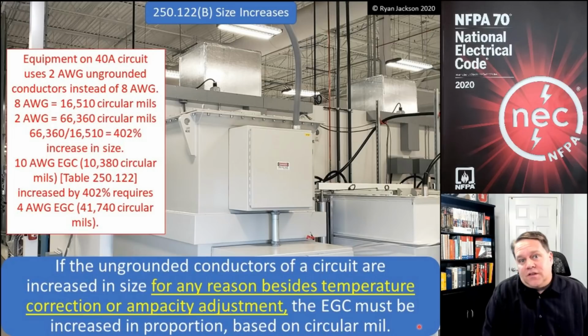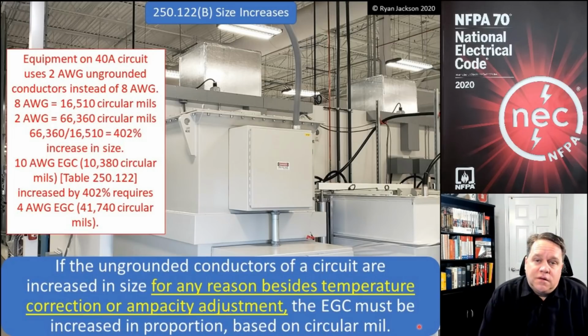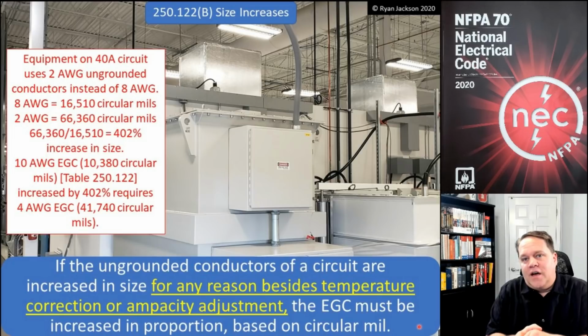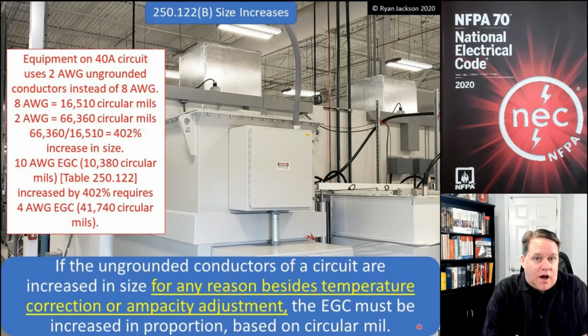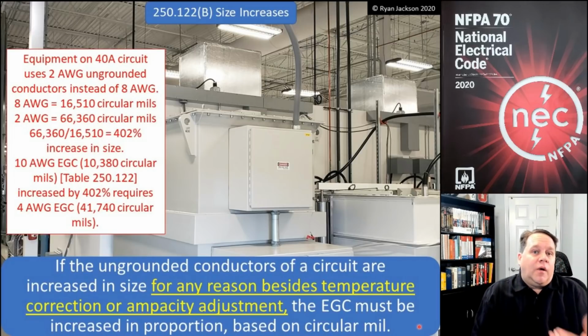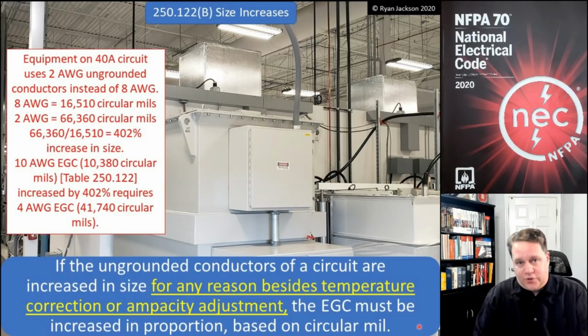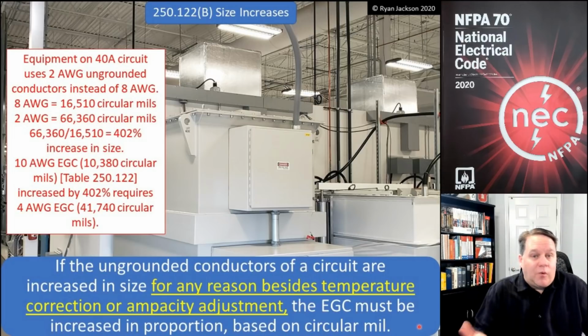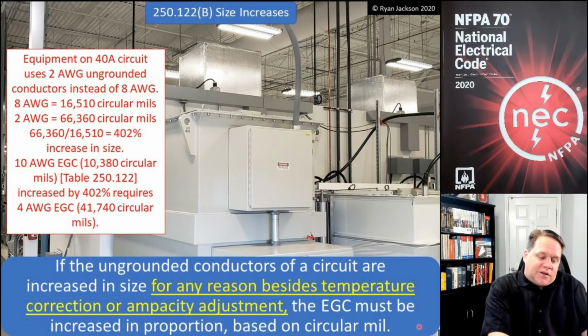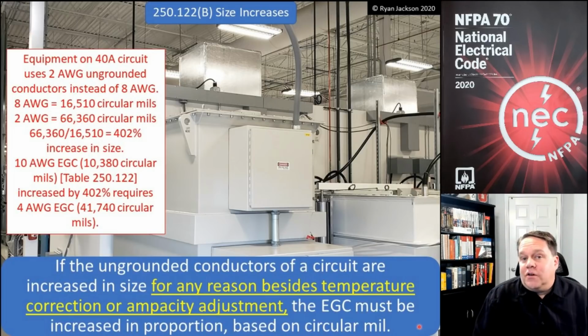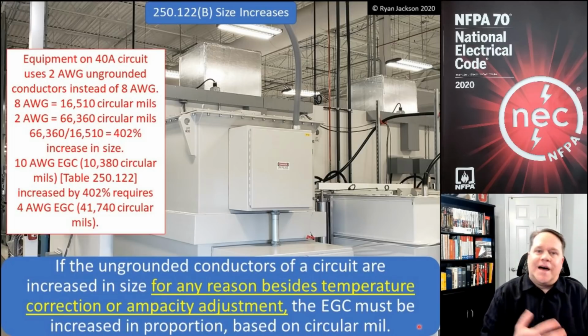But if you really want to read this section with a magnifying glass, it's a violation. Because a 30-amp circuit means that the size of the equipment ground has to be the same size as the ungrounded conductor. Right? Remember our example with the parking lot. So now we have an absurdity. Think about this for a second. You would have to rip out that wire and special order some wire if we wanted to use 8-gauge wire with an 8-gauge equipment ground. Or how else could you solve it? Well, maybe put it on a 40-amp breaker. Now, a 40-amp breaker requires more current to trip, so we're making the situation worse, but we're making it code compliant now. And then if I look at the nameplate on the air conditioner, though, it says, hey, maximum overcurrent device is 30 amps. So now I'm back to square one.